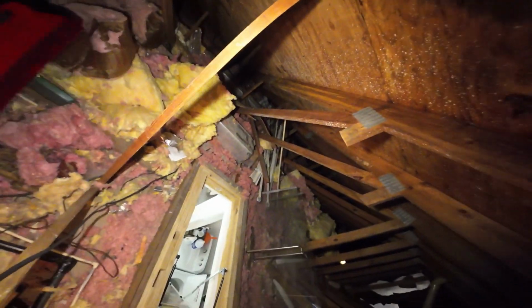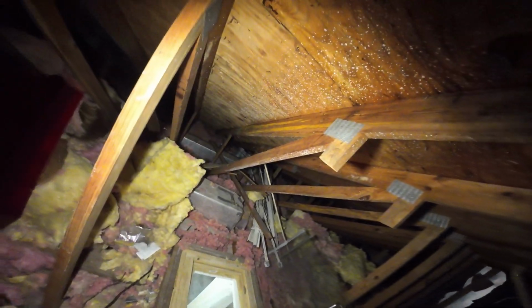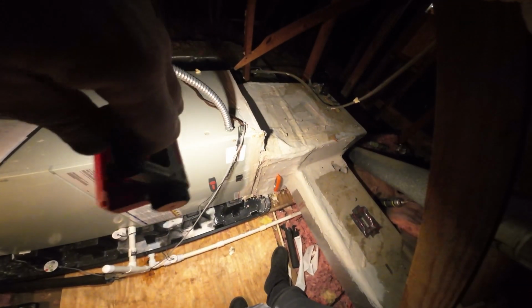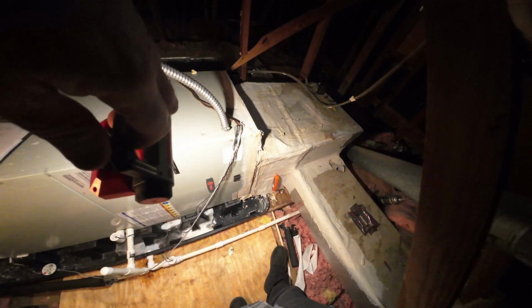It looks like all the ductwork for the first floor. But yeah, they need some new ductwork, that's for sure. If it's usually in the closet and I can't access the ductwork as well, I'll do a static pressure check. I'm not going to do one on this one because of all the ductwork damage. It'd be pointless.